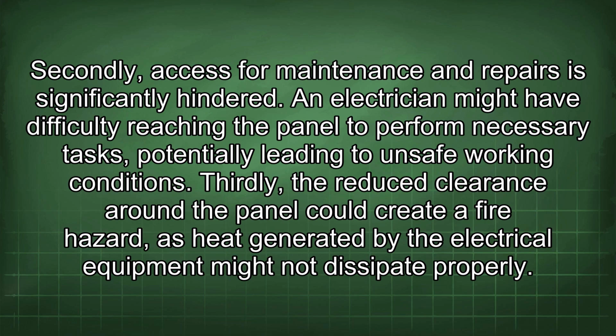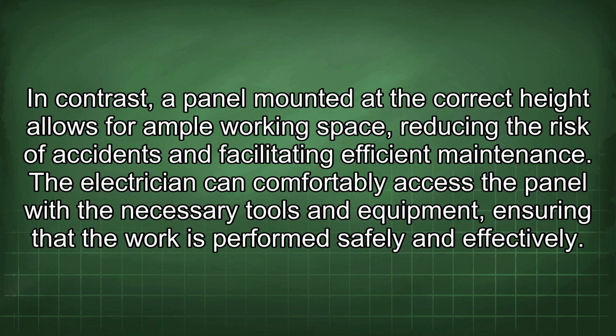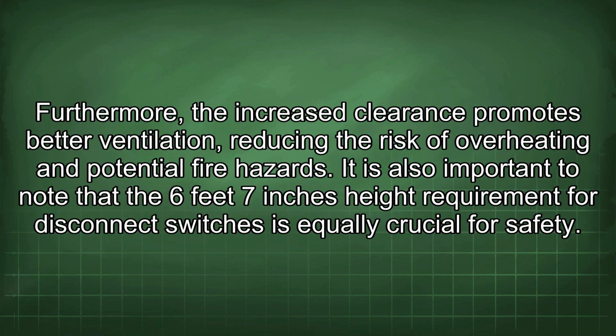Thirdly, the reduced clearance around the panel could create a fire hazard, as heat generated by the electrical equipment might not dissipate properly. In contrast, a panel mounted at the correct height allows for ample working space, reducing the risk of accidents and facilitating efficient maintenance. The electrician can comfortably access the panel with the necessary tools and equipment, ensuring that the work is performed safely and effectively. Furthermore, the increased clearance promotes better ventilation, reducing the risk of overheating and potential fire hazards.